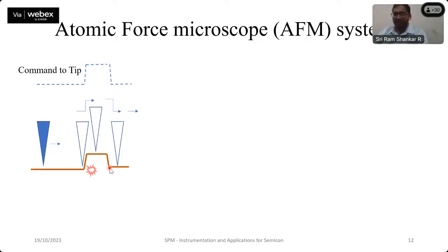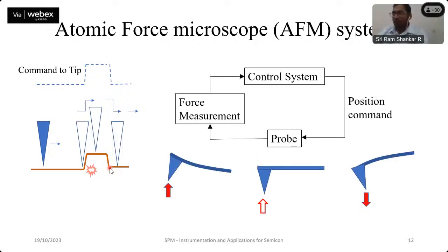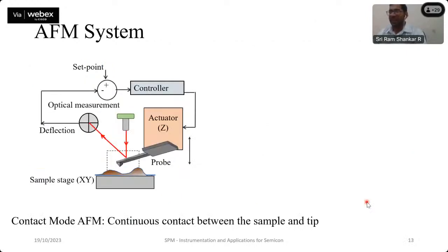So based on this we need to construct the overall AFM instrumentation system. What we are doing is we are borrowing some concepts from control systems or feedback control systems. From the probe we need to make a force measurement, and based on the measured force we need to run our control system or control algorithm that generates a position command to move the probe either up or down. Such a system can be visualized this way.